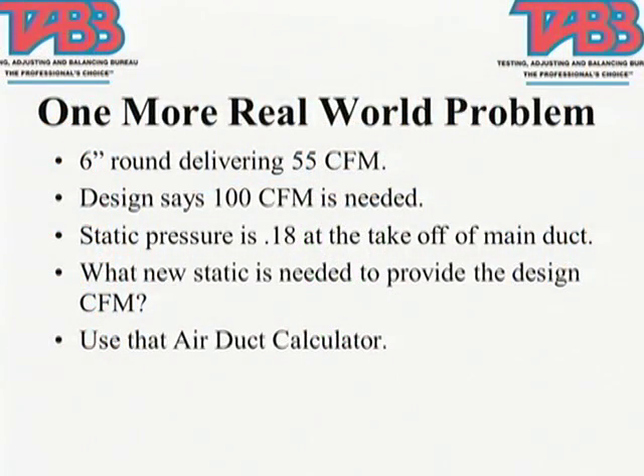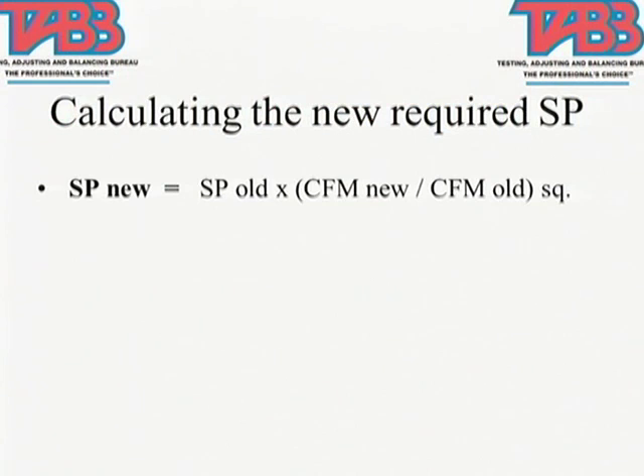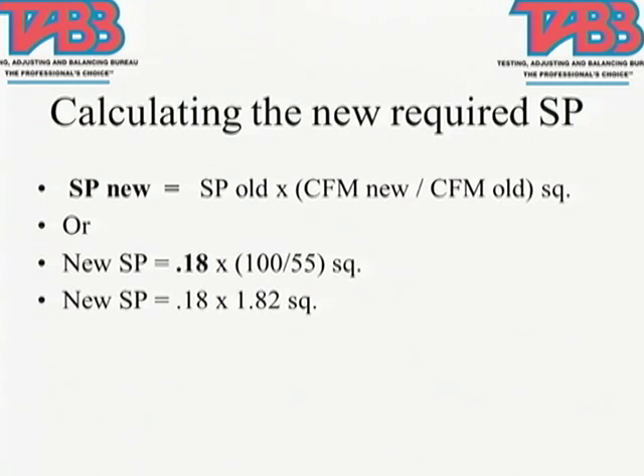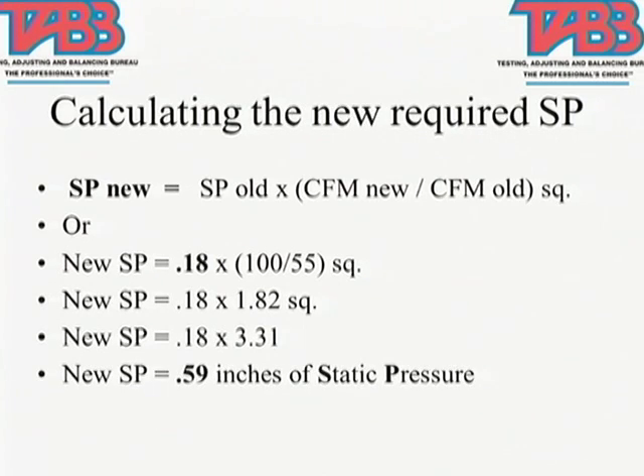One more real-world problem that I like to look at: say we have a 6-inch duct delivering 55 CFM and the design says 100 CFM. We took our static pressure inside the duct and it was at 0.18 inches. I like to calculate what the new static pressure is to deliver the proper amount of air. That's the second affinity law on our little paper calculator. We say that the new static pressure equals the old static pressure, that 0.18, times the new CFM divided by the old CFM, squared. As we work through the problem, there's our math, and we multiply that out, which gives us a new static pressure of 0.59 inches.